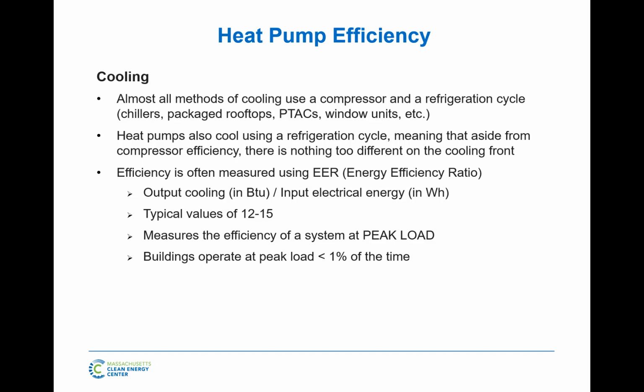However, that only happens under 1% of the time. For a generic building, this building, the equipment in this building right now, which I don't know what it is, I haven't looked at it, is sized for peak load. This building is sized on July 31st at 2 p.m. when it's the hottest day of the year, at least in the books, right? Hottest time, the equipment is sized to keep that building satisfied at that point. So it's that size. Every other time, like today, this equipment is running at part load, maybe 20% load.